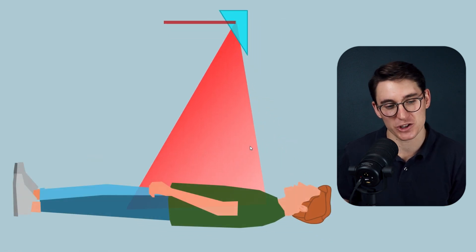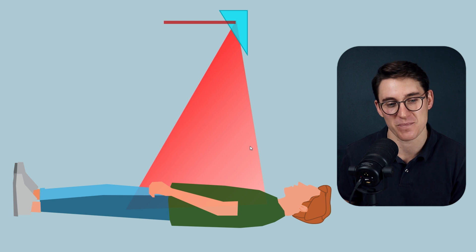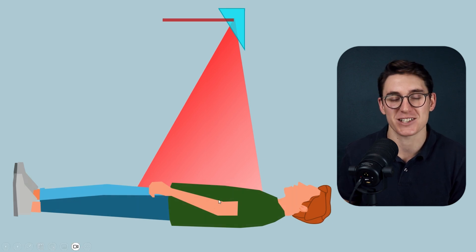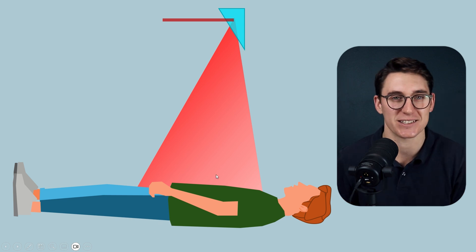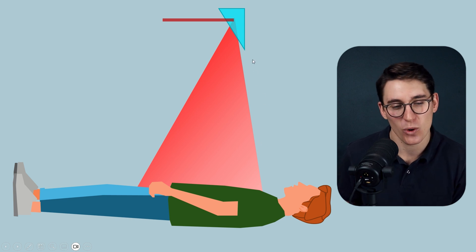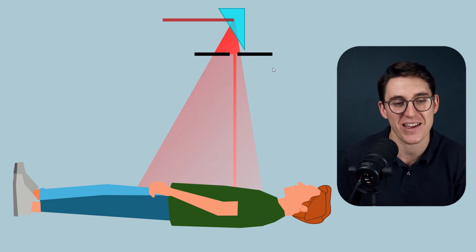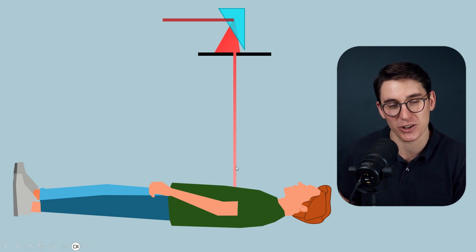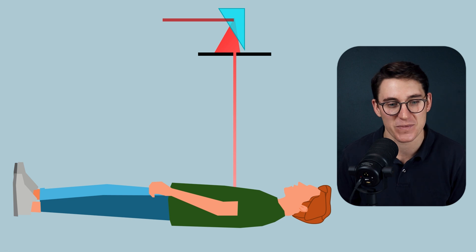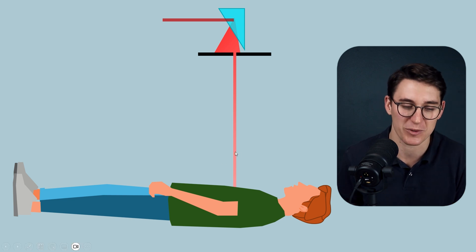In CT imaging, the anode heel effect works slightly differently. In x-ray imaging, you'd place the more intense part of the beam over a denser region to even out the fluence reaching the detector. In CT imaging, the anode lies parallel to the x-y plane we are imaging, and we collimate the beam very tightly — creating a very narrow beam width. The anode heel effect doesn't play much of a role because we've got such a narrow beam in the z-axis. The anode heel effect also doesn't happen in the x-y plane because that anode angle stays the same parallel to the beam being generated.